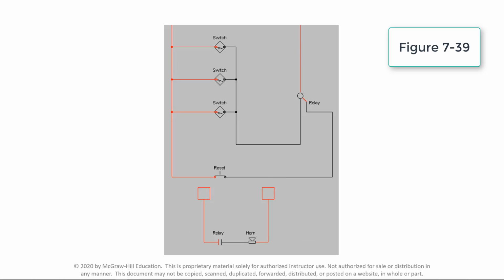This video demonstrates the operation of a battery-operated latching alarm circuit. Latching relays are used in applications where power must be conserved, such as a battery-operated device. This circuit uses a latching relay to conserve power. Regardless of whether the circuit is reset or latched, there is no current drain on the battery.